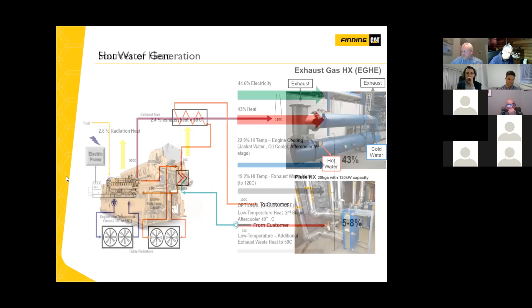So hot water is the most common application we see for heat recovery on a recip. You can see from this example, we are in fact dumping low temperature heat. That's this circuit. Can everybody see my arrow, by the way? Somebody nod. Yes, we can. That's it. Yeah, so if we follow the flow of this, this is the jacket water heat leaving the engine after the thermostats crack open at 95 degrees C, goes through the plate and frame heat exchanger, and then back to the engine at 85 degrees C.